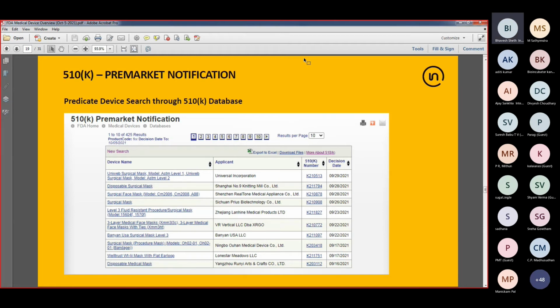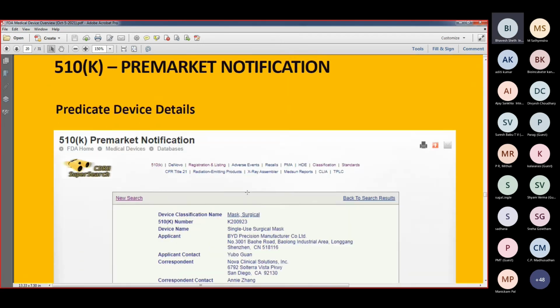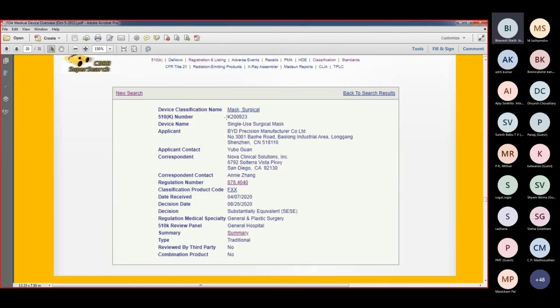Now, you're not going to get much beyond the product name through this page alone. So if you select one of these products, you'll find more information about that predicate device. You'll find the 510K number, of course, the device name, the applicant information, but now you also find the applicant's registered business address. So you know what region that manufacturer is based in, and from where they are selling the product in the US. You also find information that you typically find in the device classification database. You find the regulation number, you find the product classification code, and the approximate timeline when the 510K was received and the decision was made.